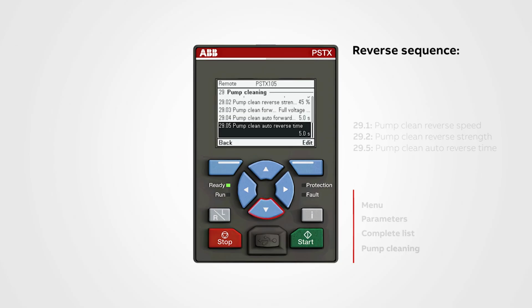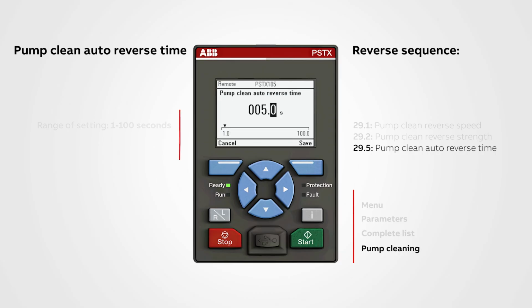The last parameter for the reverse rotation is 29.5, pump clean auto reverse time. This sets the number of seconds to run reverse for one cleaning sequence for the automatic pump cleaning. The range of this setting is between 1 to 100 seconds. The default value is 5 seconds.